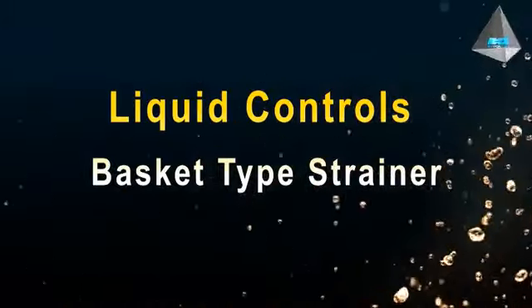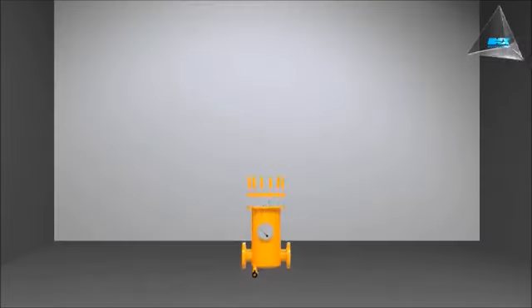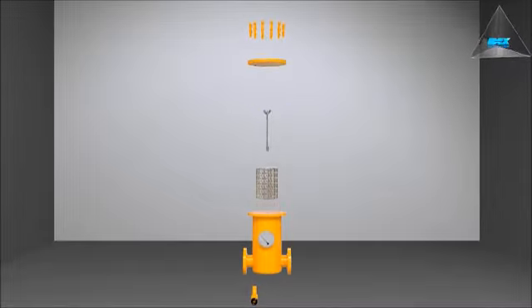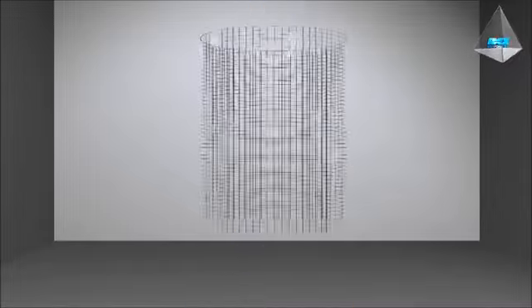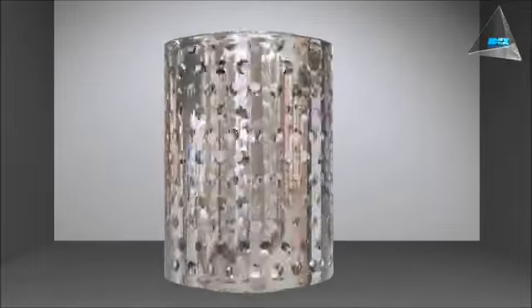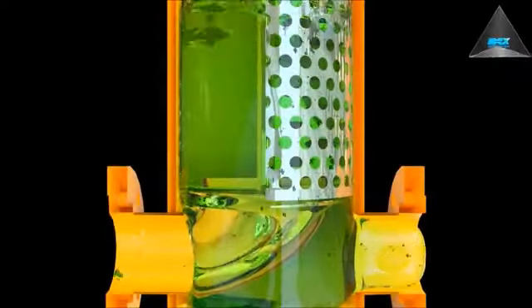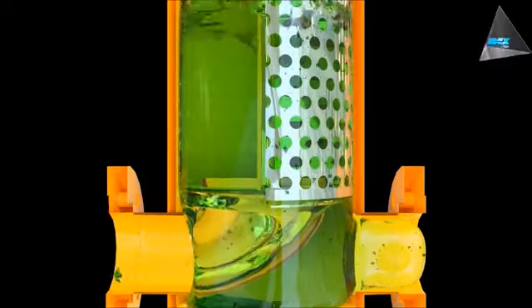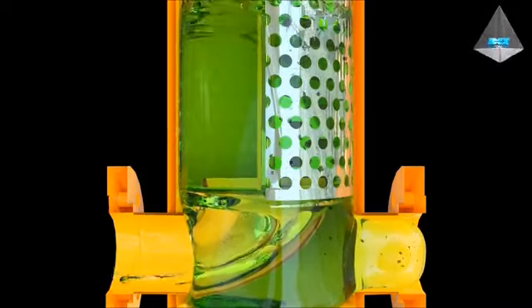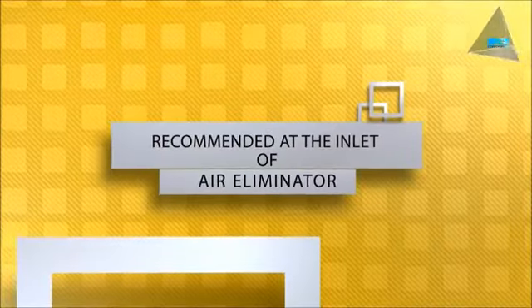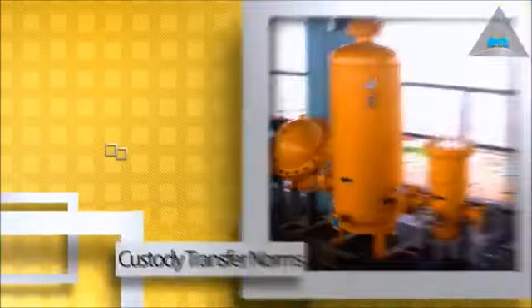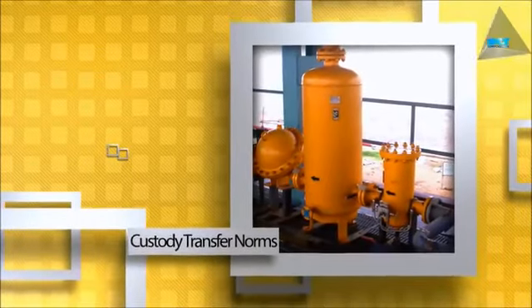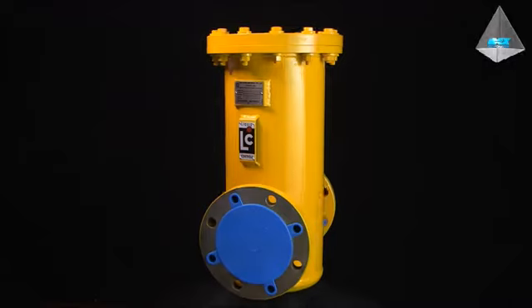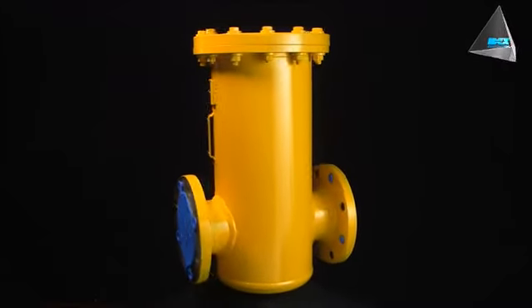Liquid Controls basket type strainer. Strainers help to protect meters from serious damage caused by burrs dislodged from new piping, pipe scale or foreign material. They are always recommended at the inlet of the air eliminator in a metering system in line with custody transfer norms. They act as a low-cost protection for the meter housing.